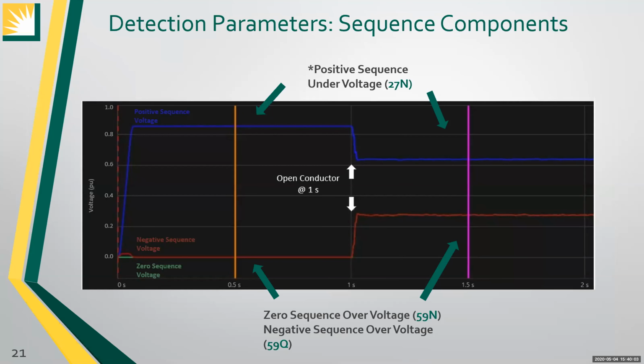The graph here shows the 3 voltage sequence components of our distribution system model before and after an open conductor event occurs at roughly 1 second of simulation runtime. We analyze the simulation results half a second before and after the open conductor event because this represents our detection window of 30 system cycles, which is equal to half a second. This is represented by the orange and magenta vertical lines you see on the graph. Half a second before the open conductor event, the system's 0 and negative sequence voltage magnitudes are nearly 0, and the positive sequence voltage magnitude is about 0.83 per unit. This represents the nominal values we wanted to see for a healthy system for our model.